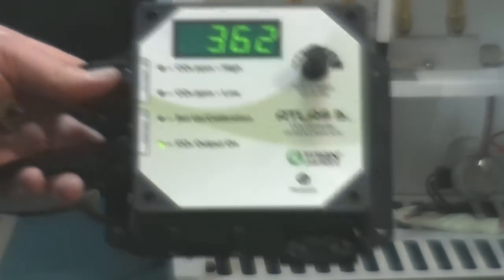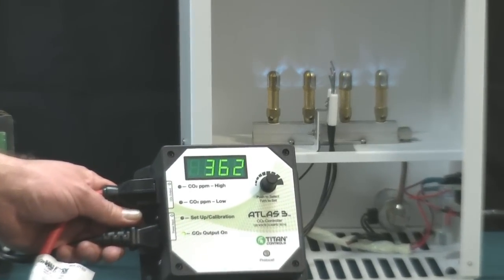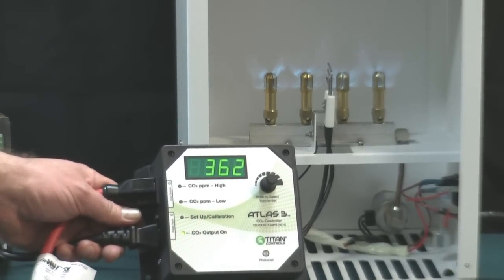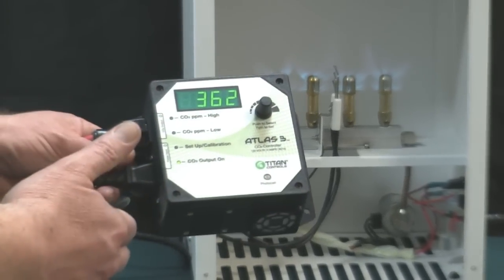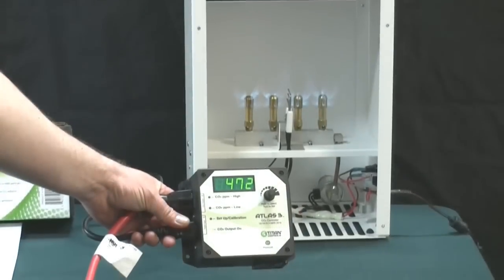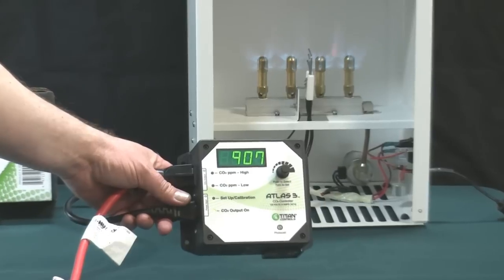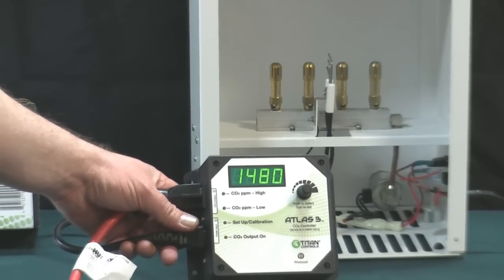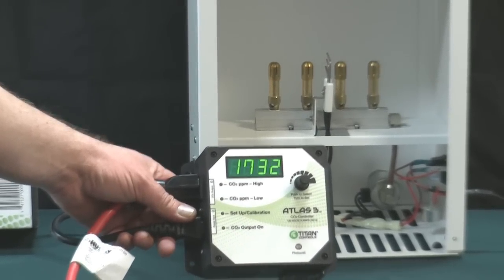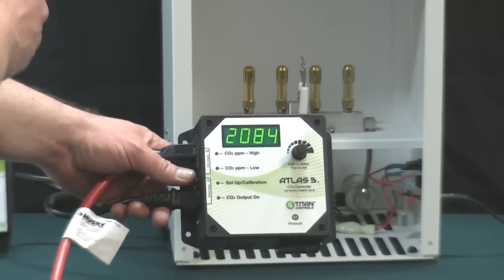Let me show you how this works. Right now, as you can see, the generator is active and is 362 parts per million. If I blow into this and take the parts per million over my set point, watch what happens. As you can see, the CO2 is raising. Now, you see we've exceeded our set point and it's deactivated the CO2 generator.